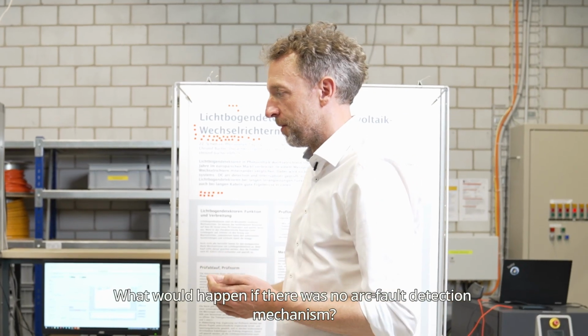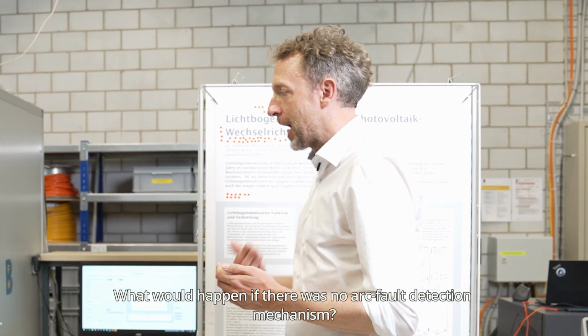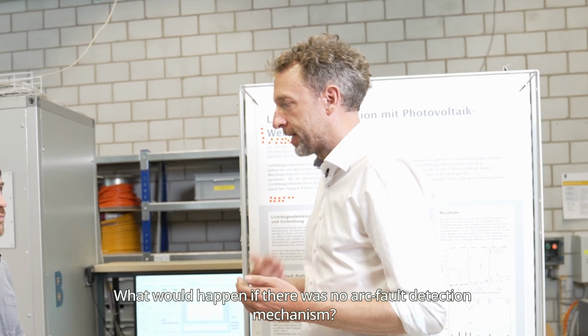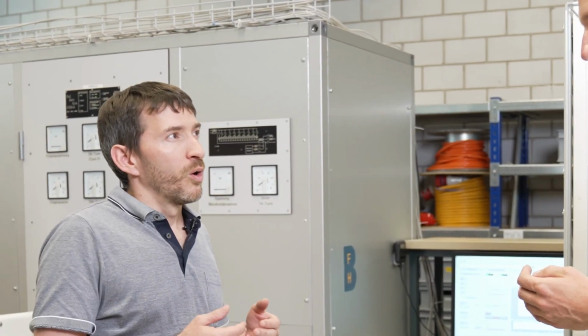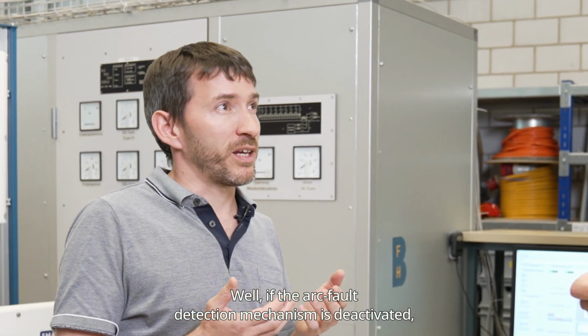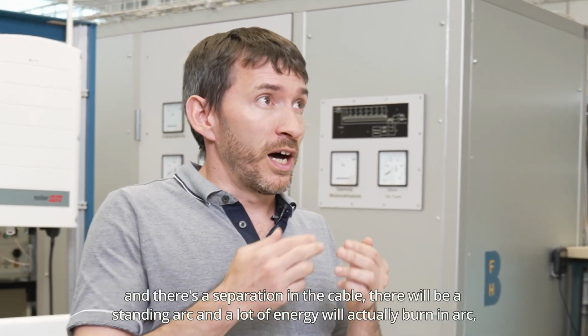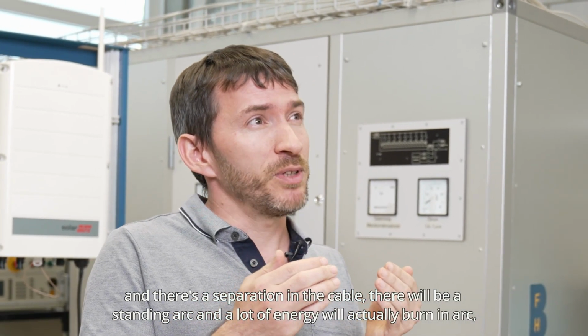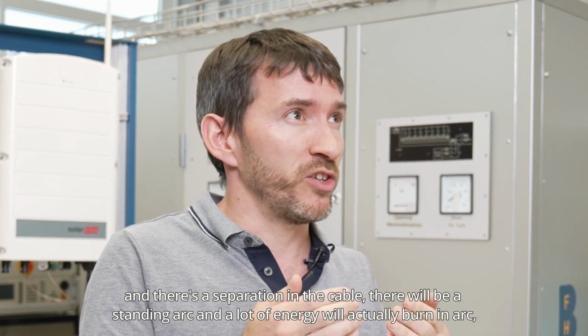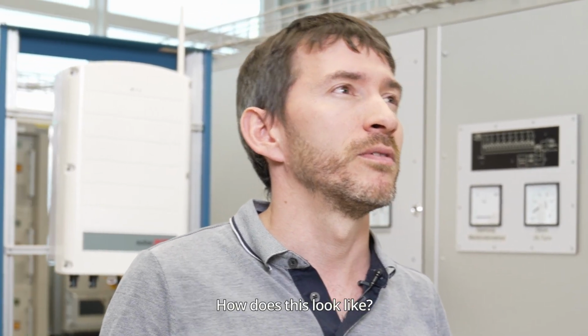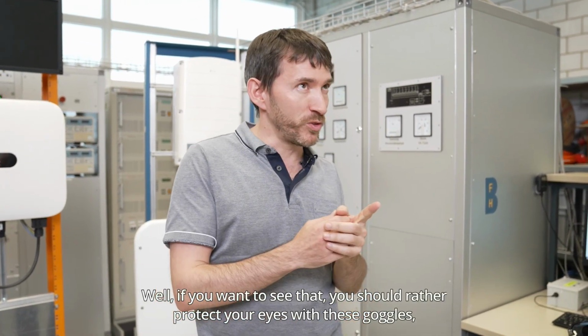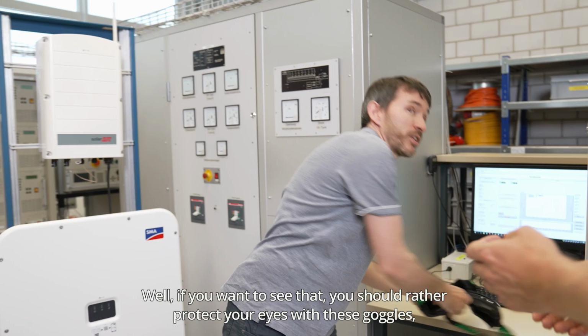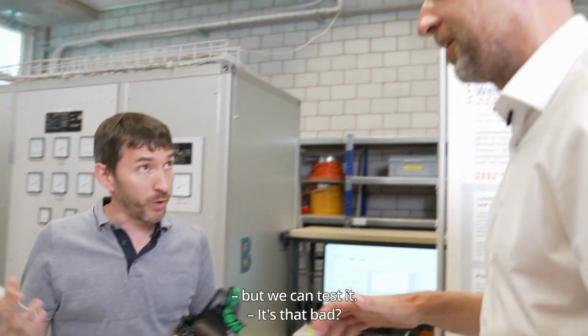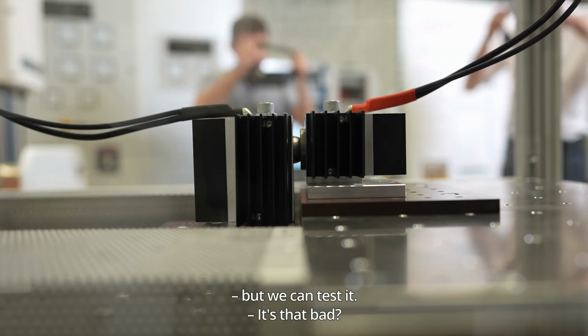What would happen if there was no arc fault detection mechanism? Well, if the arc fault detection mechanism is deactivated and there is a separation in the cable, there will be a standing arc and a lot of energy will actually burn in this arc and the temperatures can get very hot. How does this look like? Well, if you want to see that, you should rather protect your eyes with these goggles. Okay. But we can test it. Is that bad?